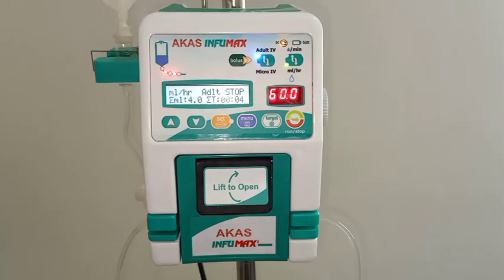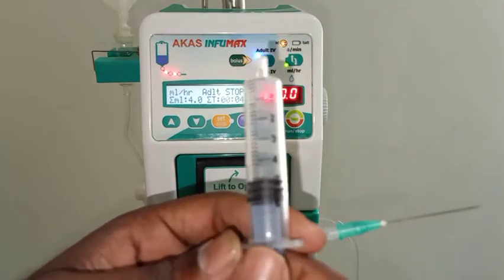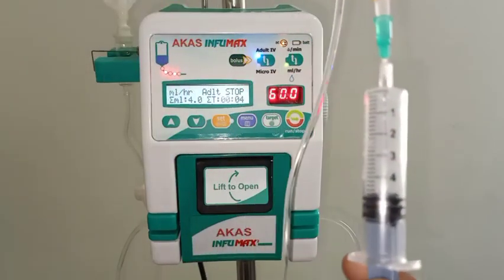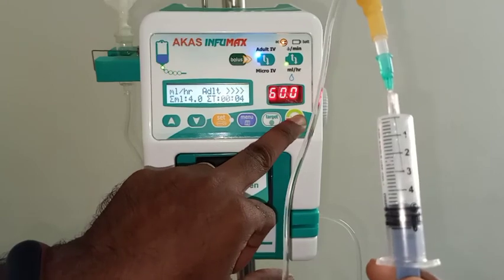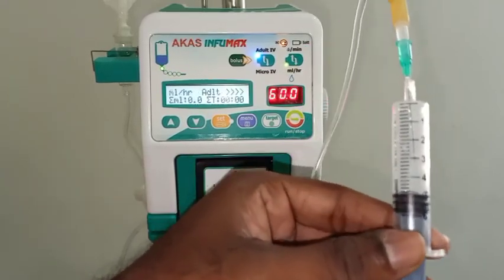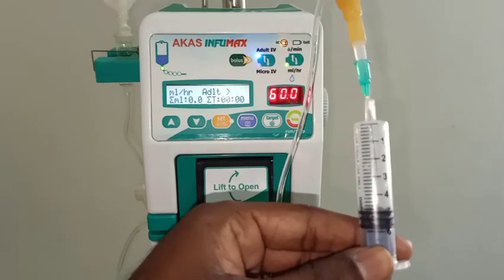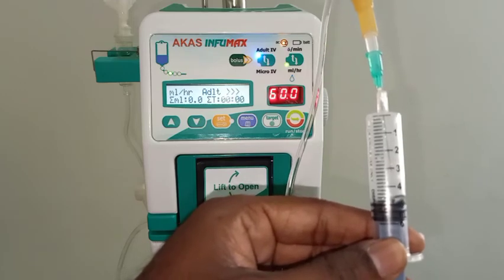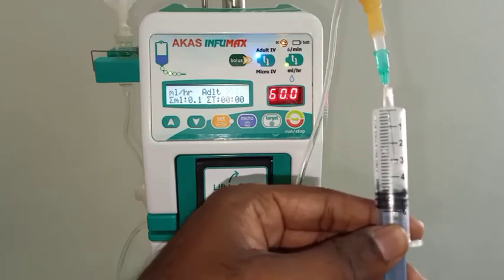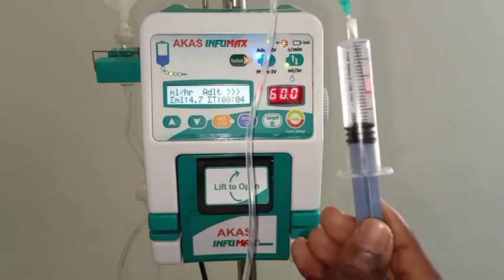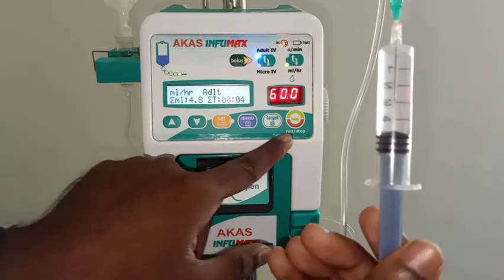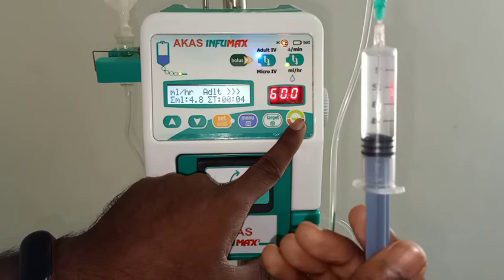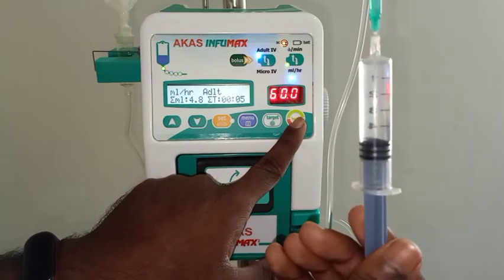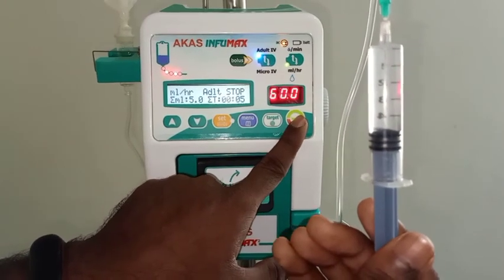Now we can check the accuracy after calibration. Same procedure. I have set the flow rate of 60 ml per hour and taken a 5 ml empty syringe, inserted the IV tube into the empty syringe, and long pressed the run stop key to clear and run the infusion. Now the drug has entered into the syringe. Now see, the syringe is going to fill 5 ml. So it's filled. I just press the stop key.